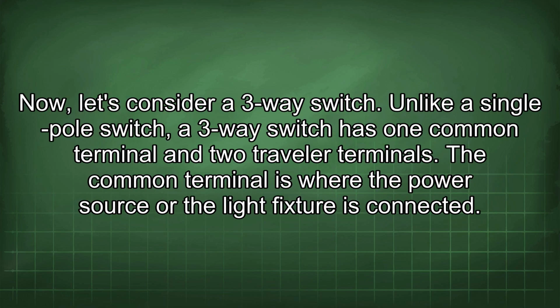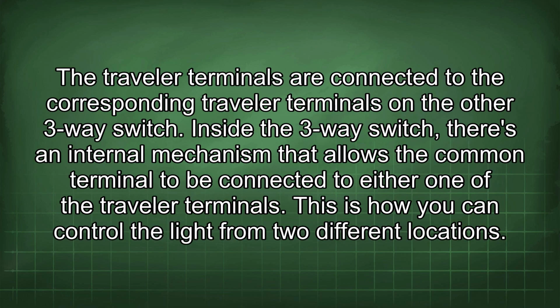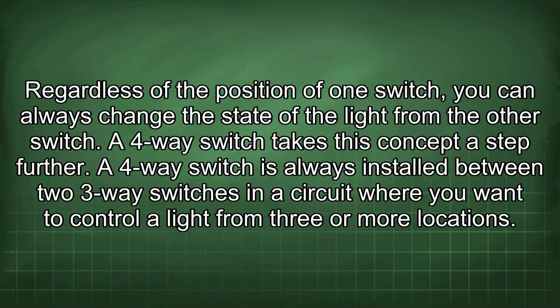Now, let's consider a three-way switch. Unlike a single-pole switch, a three-way switch has one common terminal and two traveler terminals. The common terminal is where the power source or the light fixture is connected. The traveler terminals are connected to the corresponding traveler terminals on the other three-way switch. Inside the three-way switch, there's an internal mechanism that allows the common terminal to be connected to either one of the traveler terminals. This is how you can control the light from two different locations. Regardless of the position of one switch, you can always change the state of the light from the other switch.